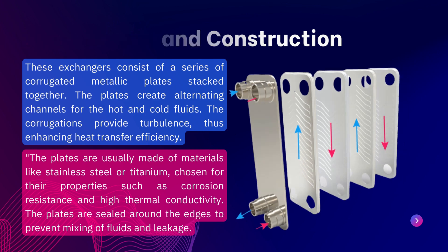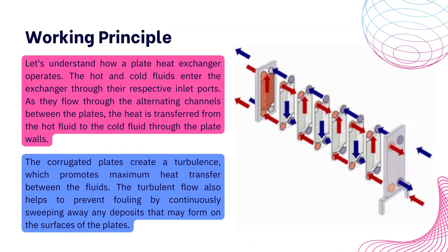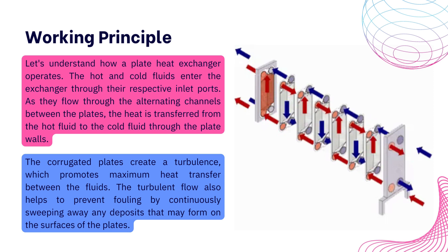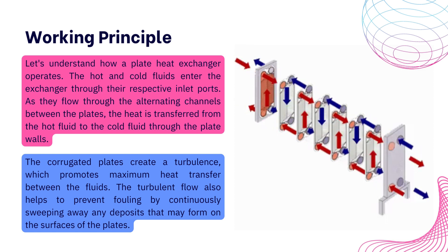Now let's understand the working principle of a plate heat exchanger. Hot and cold fluid enter through their respective inlets and flow in channels between the plates alternately. Heat transfer from hot fluid to cold fluid takes place through the plate wall, which also prevents intermixing — this is indirect heat transfer. The corrugations create turbulence, resulting in maximum heat transfer between the fluids. The turbulent flow also helps in the continuous removal of foulants and deposits from the surface of the plates.